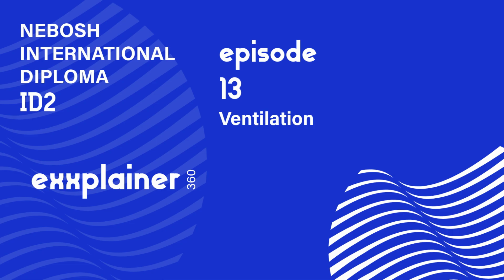Okay, last part. The discharge, getting the cleaned air back outside. Seems simple, just blow it out. But again, physics matters. The discharge stack, the chimney, needs to be tall enough to get the exhaust stream above the building's boundary layer. Boundary layer. What's that? Think of it like a sort of sticky, slow-moving layer or bubble of air that clings to the surfaces of the building, the walls, and the roof. It's caused by wind resistance.